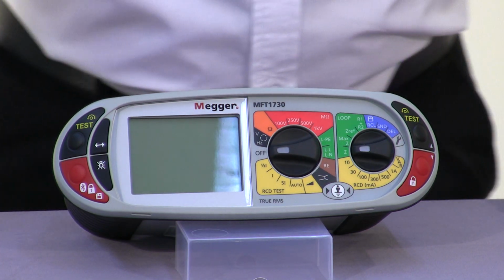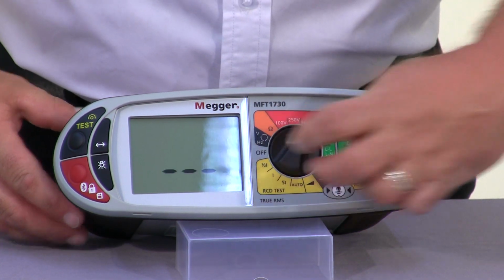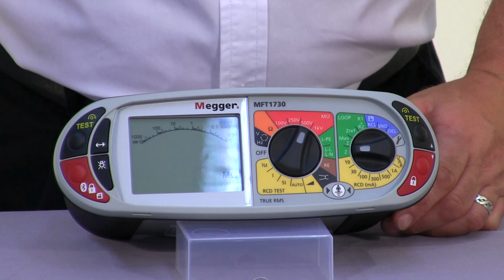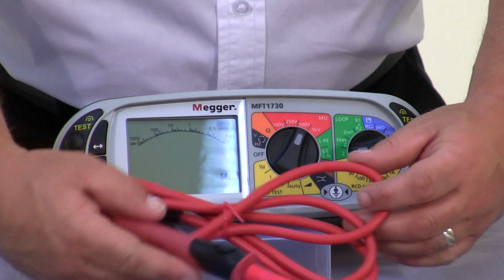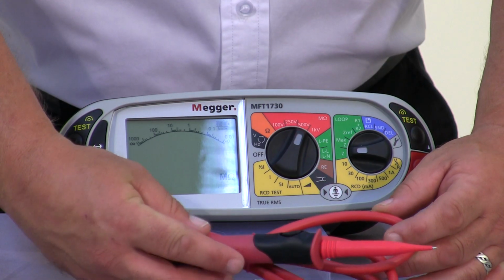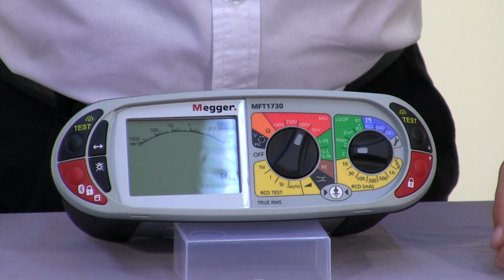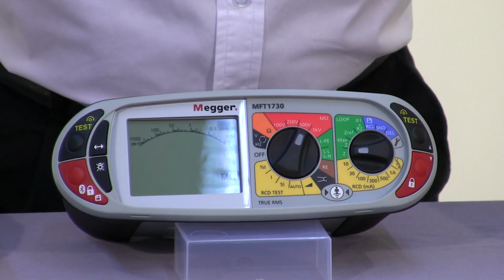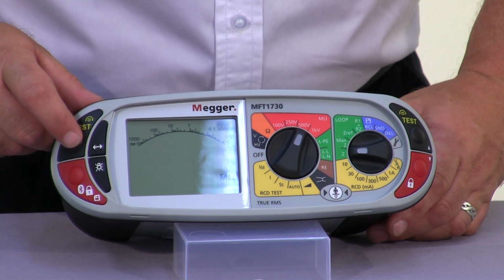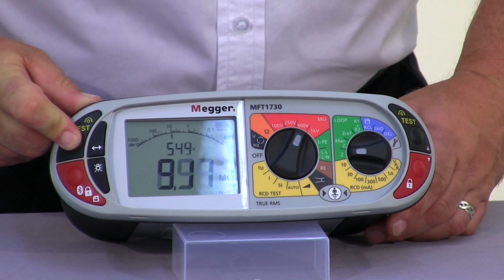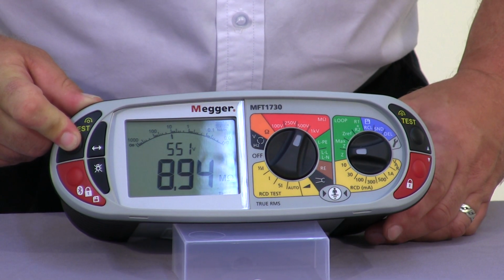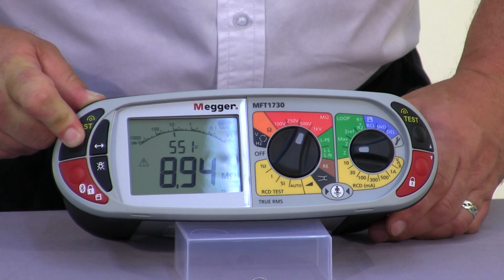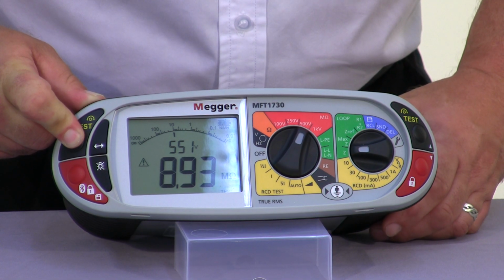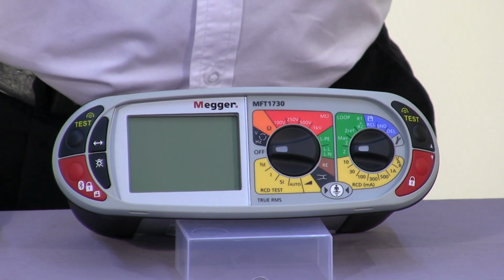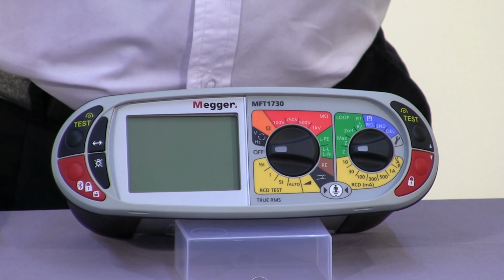Insulation testing on the MFT1700 series is just a case of dialing up our desired test voltage and pressing our test button. One of the things that you get with the 1720 and the 1730 models is the remote switch probe. This just allows you to maintain two-handed operation, and that is available as an accessory with the MFT1710. So we have a known resistance, we've dialed 500 volt insulation, and we press the test button. Now the upper of the two parameters will now indicate to make sure that we're actually conforming with the 17th edition and maintaining our voltage output. And as you can see, we've got a reading here of 8.94 megohm. At this point, what I'd like to do is just show you the input protection that's built into every model of the MFT1700 series.